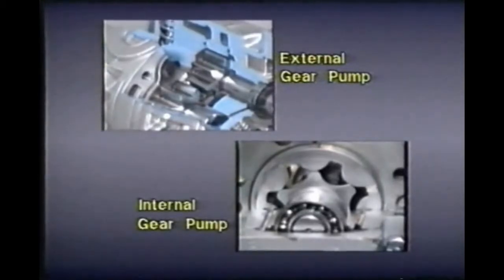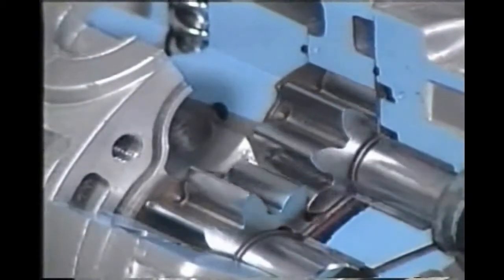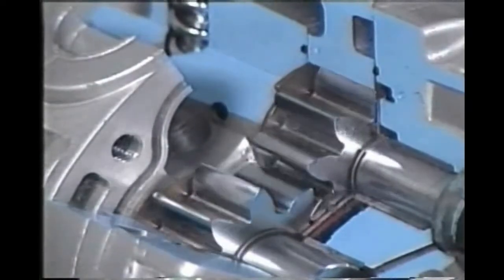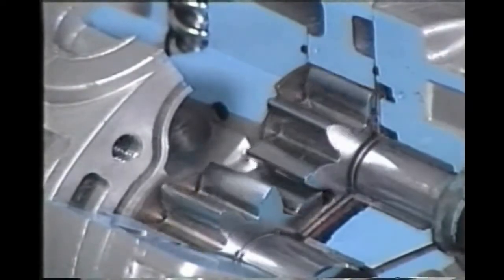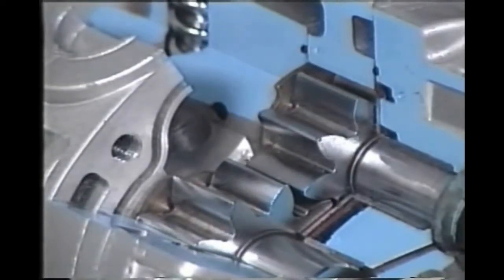Now let's look at the gear pump. These simple, economical pumps use two gears that turn and mesh inside a tightly fitting housing. There are two kinds: external gear pumps and internal gear pumps. The teeth of the external gear pump, often called a spur gear pump, take fluid from the pump inlet and carry it between the teeth and the housing, then discharge it through the outlet port.